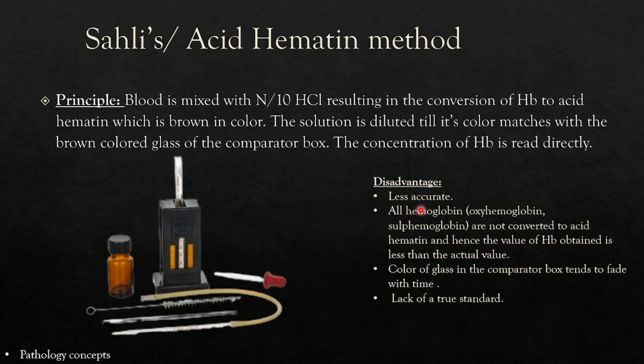Saheli's (acid hematin) method principle: blood is mixed with N/10 HCl, resulting in conversion of hemoglobin to acid hematin, which is brown in color. The solution is diluted until its color matches the brown color glass of a comparator box, and the concentration of Hb is read directly. Disadvantages: it is less accurate; not all hemoglobin forms like oxyhemoglobin and sulfhemoglobin are converted, so the value obtained is less than actual. The comparator box glass color tends to fade with time, and there is no true standard available. It is only used in under-resourced laboratories.